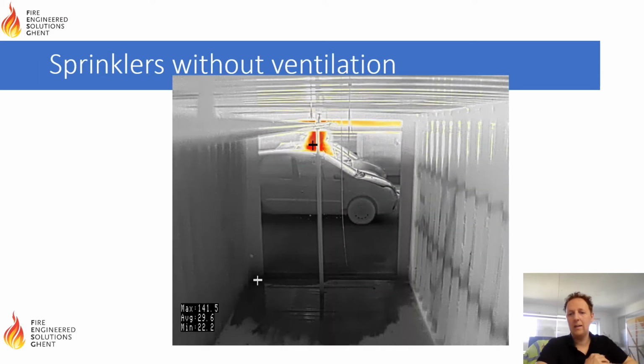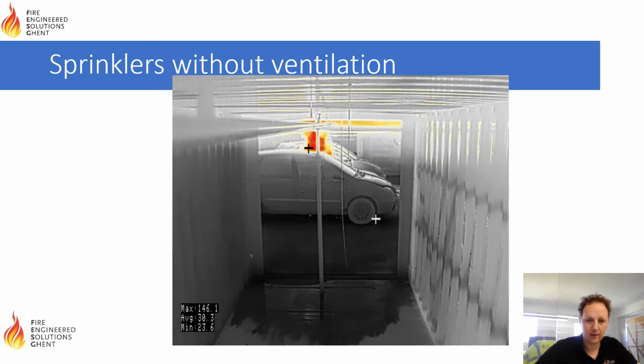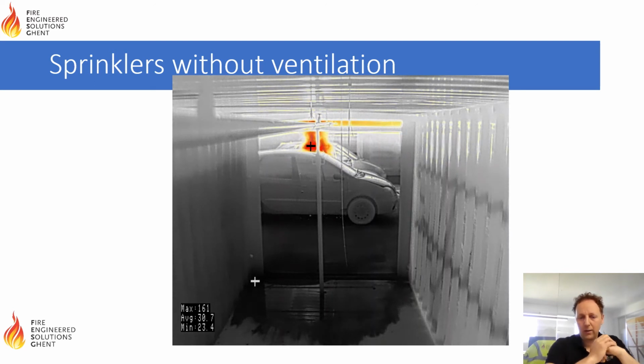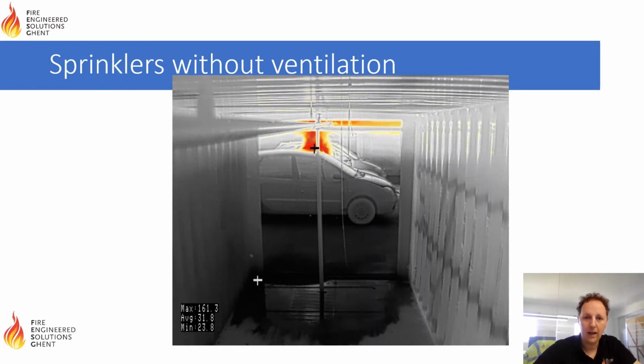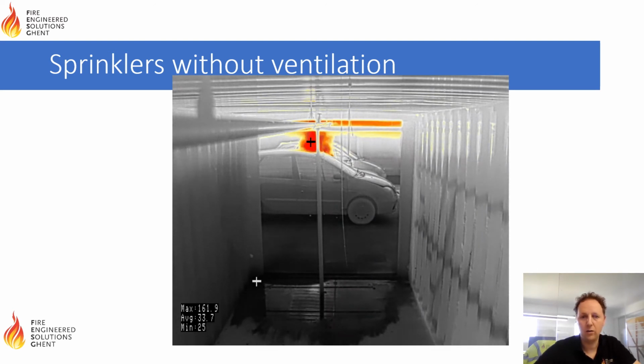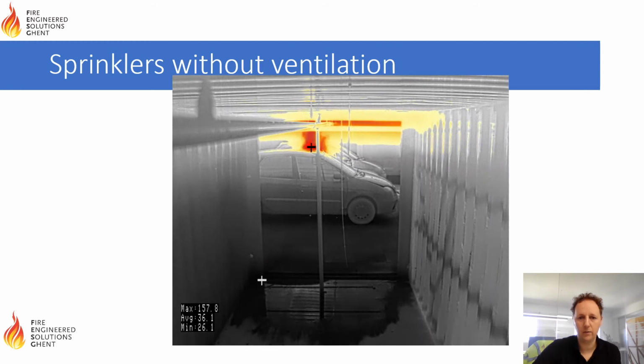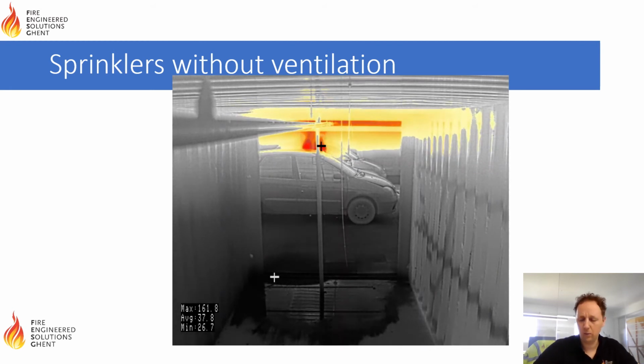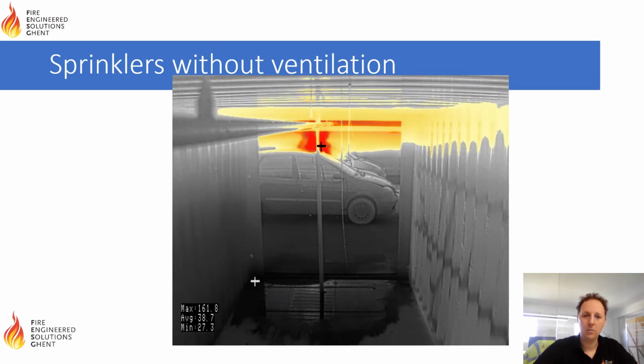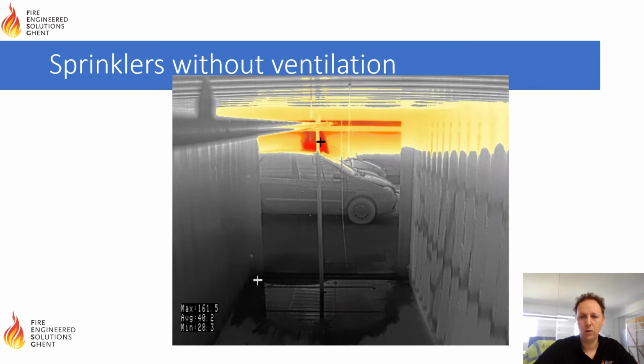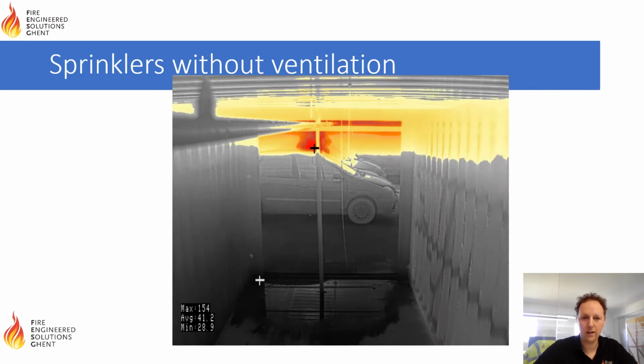Okay, so let's have a look at a test where there was a sprinkler system with no ventilation. So we're looking from thermal imaging camera. Let's start the test. So the fire was started with a wood crib on the passenger seat. The window of the driver's seat was open, and the black cross you see is a temperature measurement of the smoke plume coming out of the driver window. So we see a temperature around 160 degrees of smoke coming out of the driver's window. You see the heat accumulation in the container. So at this point, there's no visibility without the thermal imaging camera.